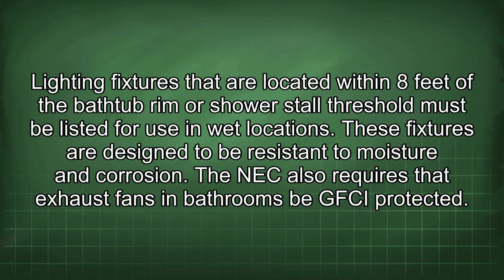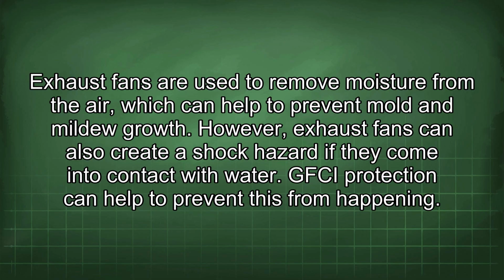The NEC also requires that exhaust fans in bathrooms be GFCI protected. Exhaust fans are used to remove moisture from the air, which can help to prevent mold and mildew growth. However, exhaust fans can also create a shock hazard if they come into contact with water. GFCI protection can help to prevent this from happening.